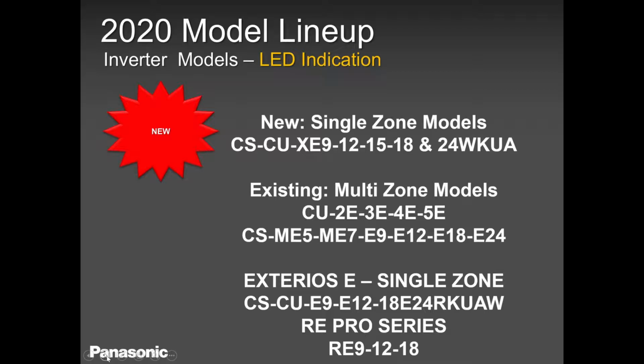But the WKUA at the moment, we can only install it as singles, and it has been approved for only a 3 zone outdoor unit at the moment. So these are single zones, but they can also be installed at the moment for only the 3 zones. The 2, 4 and 5 are yet to be approved. As for the RKUAs, you can install them single as well as multi. Okay, guys?